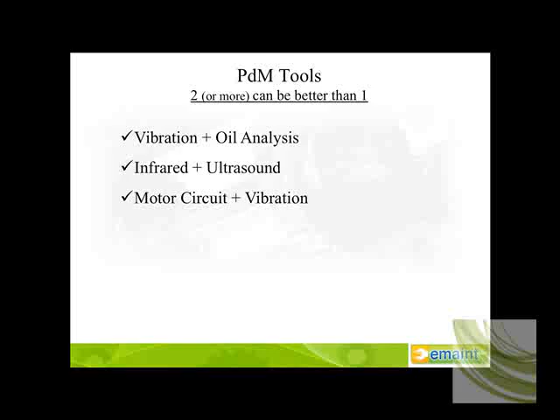Combining vibration and oil analysis. We talked about oil analysis being able to see what the particulate makeup is, determine what particles exist within that lubrication on that asset. So combining oil analysis and vibration analysis together gives you a much better handle on what's taking place with that asset.